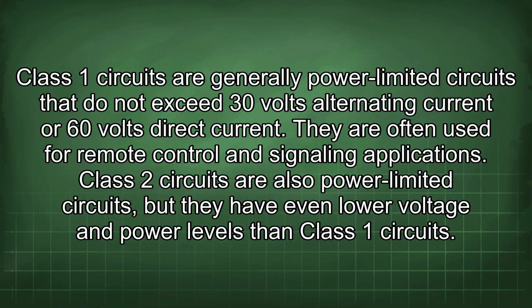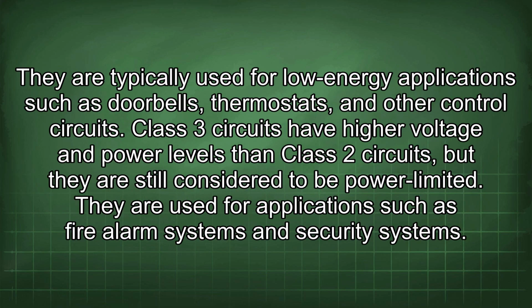Class 2 circuits are also power-limited circuits, but they have even lower voltage and power levels than Class 1 circuits. They are typically used for low-energy applications such as doorbells, thermostats, and other control circuits. Class 3 circuits have higher voltage and power levels than Class 2 circuits, but they are still considered to be power-limited. They are used for applications such as fire alarm systems and security systems.